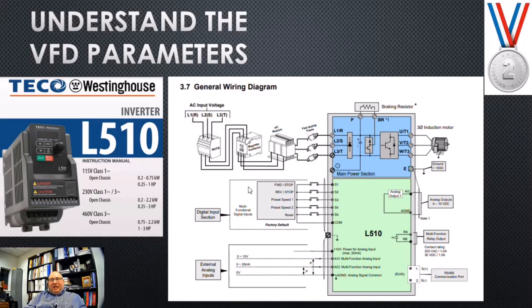There is a predefined set number of inputs called digital inputs. We have our forward command. This is where we would do a run forward, run reverse, which we're not going to run in reverse. Then you have preset 1 and 2, and then a reset over here. Now you could use a reset in case you had to do a remote reset of the VFD where you don't have to physically visit it. There are external analog inputs. Analog inputs are going to be your 0 to 10, 4 to 20. And this is how we're going to control the speed if it's set up correctly in the parameters. We have an analog output that we could use here for feedback or for fan tracking where we want to wire in multiple VFD drives in piggyback orientation.